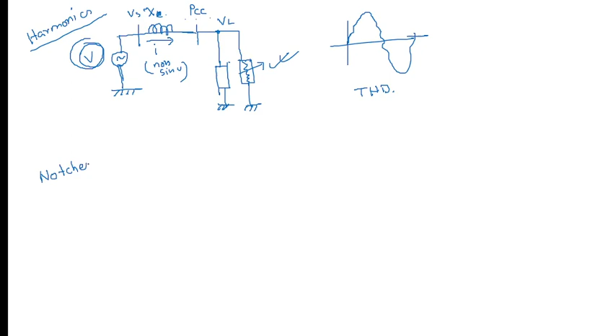Notches are also a result of non-linear loads or power converters, mostly because commutation appears in power electronic devices. There are two types of commutation: forced commutation and natural commutation. During commutation, handling the conduction from one device, like a diode or rectifier, to another causes two devices to conduct simultaneously for a very small duration. This creates a problem, like a short circuit, in the system, which creates notches.